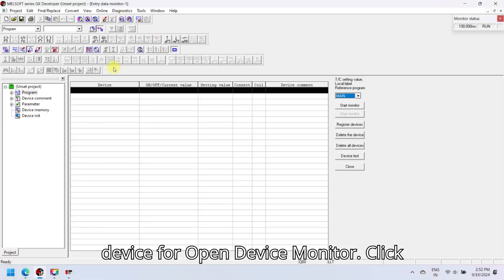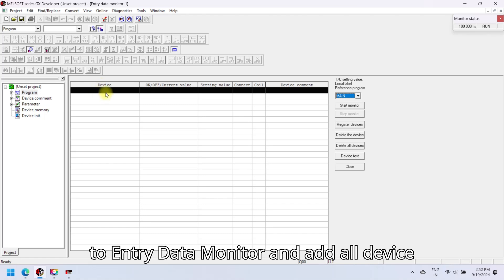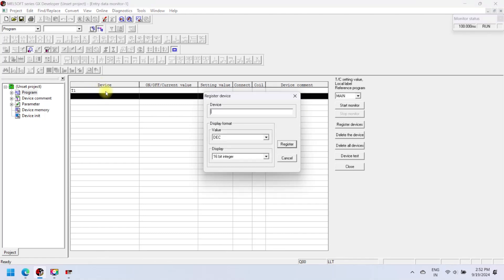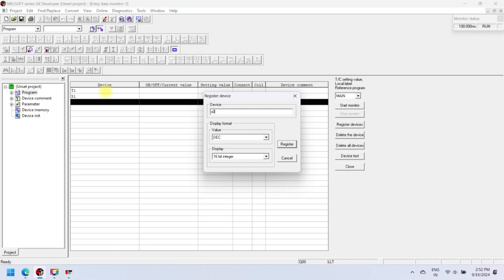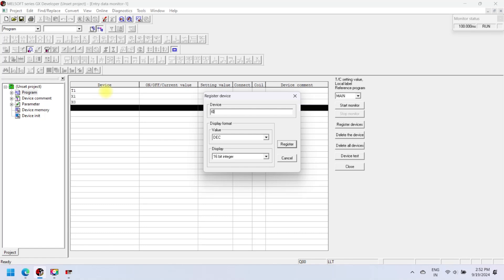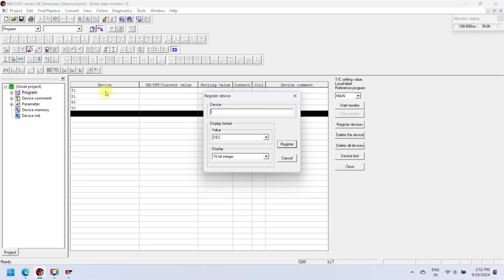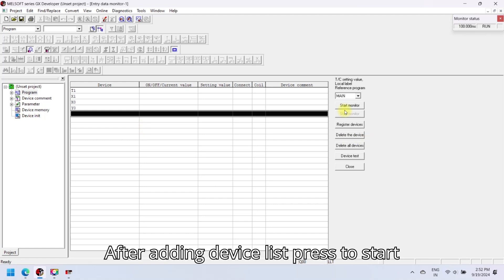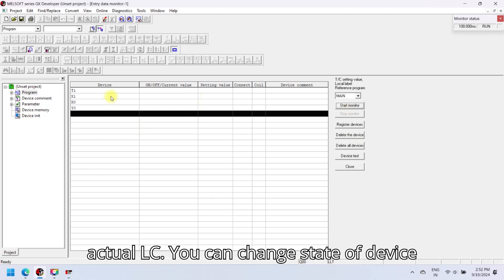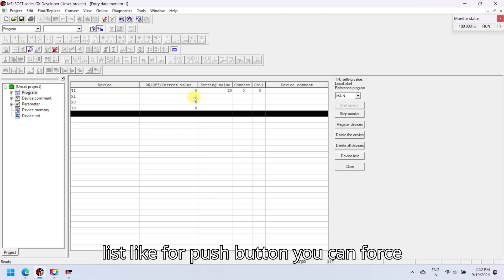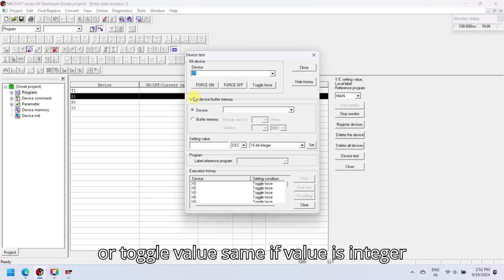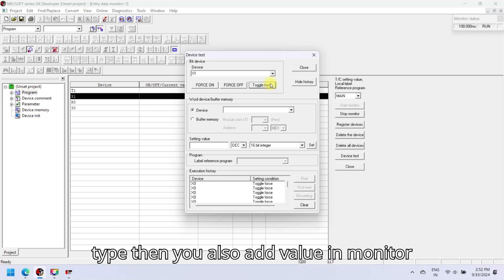To open device monitor, click entry data monitor and add all devices which you want to monitor. After adding the device list, press start monitor — your monitor table shows all actual PLC values. You can change the state of device list items; for a push button you can force or toggle the value. If the value is integer type, you can also add a value in the monitor table.